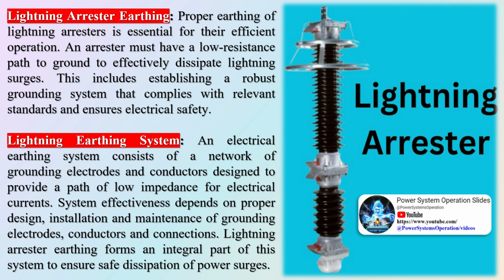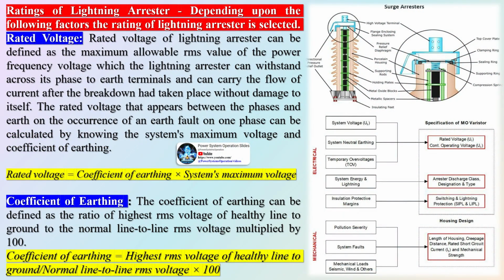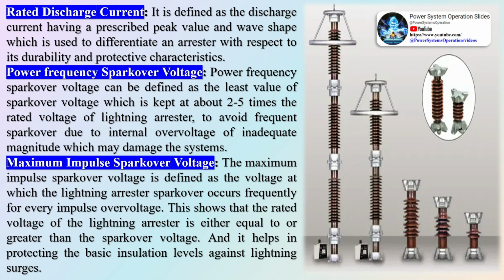Lightning arrestors have a limited lifetime as the internal varistors deteriorate with each operation. Regular inspection and maintenance are essential to ensure their protective performance. Some best practices include: visual inspections, regular checks for physical damage or contamination; testing, periodic testing of electrical characteristics to ensure proper functionality; cleaning, removing dirt, dust, and other contaminants that could affect performance; replacement, timely replacement of damaged or worn-out components; annual insulation resistance tests to check for contamination, cracks, or leakages; and five-yearly replacement or refilling of explosion vents in tank-type models. Every 10 years, varistor blocks must be replaced even if the insulation is intact. Outdoor arrestors need to be kept clean and dry. Their connections should be inspected annually.